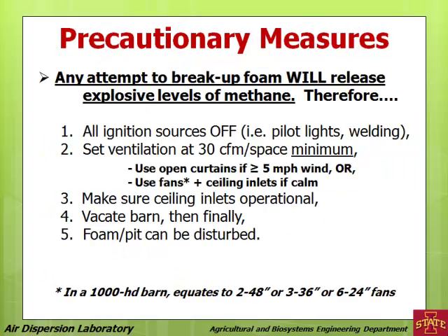Precautionary measures. So here's the bottom line, right? Any attempt to break up foam will release explosive levels of methane. That's for sure. Therefore, all ignition sources need to be off if there's any attempt to break up this foam.